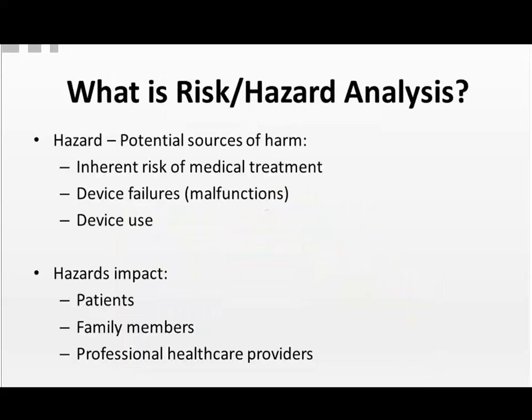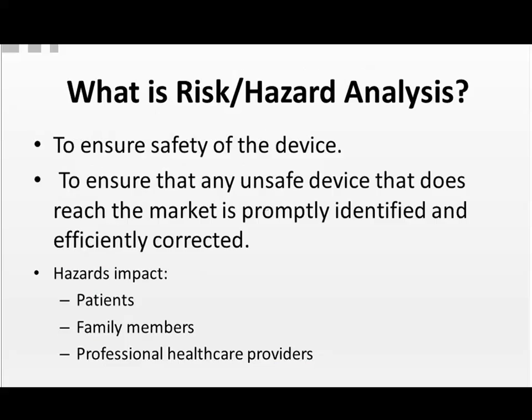Now, to continue our definitions, a hazard is a situation that poses a level of threat to life, health, or the environment. There are three types of hazards as they relate to medical devices. They include the inherent risk of the medical treatment itself, device failures, which are malfunctions, and device use. Those hazards impact patients, family members, and professional healthcare providers, with certainly the emphasis being on patients.